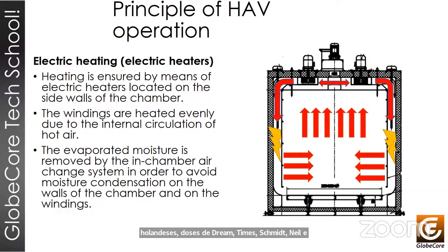This is achieved by means of optimized and uniform heat distribution using fans and air deflectors, as well as by fully fledged heating of the autoclave. Heating inside the chamber occurs due to the electrical heating elements located on the side walls of the chamber. Due to the direct heating of the medium, the temperature in the chamber rises rather quickly, which makes it possible to shorten the drying time.